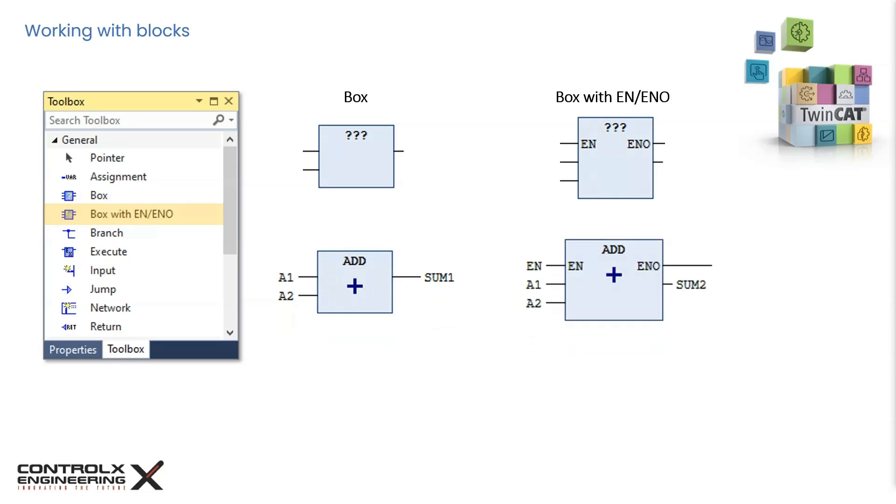Now we have the same functionality but with the other counterpart. Here the output sum2 is not updated unless the EN input is set to true. If EN stays false, then sum2 will hold on to the last computed value, even if its inputs a1 and a2 are changing. Once EN becomes true, then the output sum gets updated. This can be useful if the logic execution of certain blocks is required to be done only under special conditions.